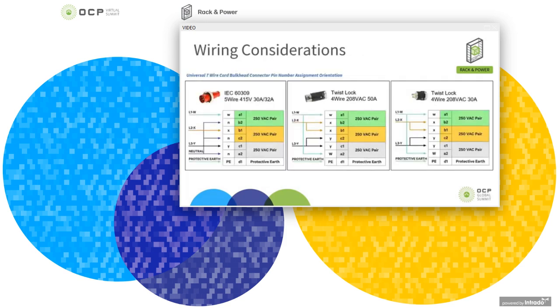So to dive a little bit more into what we saw on that last slide, where these multiple different facility cables or power cables can feed that PDU, we look back at what we're always doing: we're always distributing single phase power out of those C13 outlets, even though three phase power is coming in. So with that, the input connector that we saw had seven conductors on it. Well, if at one end of the cable we have five conductors, or four conductors in a delta, or three conductors in a single phase application, we have to kind of magically make that turn into seven conductors.